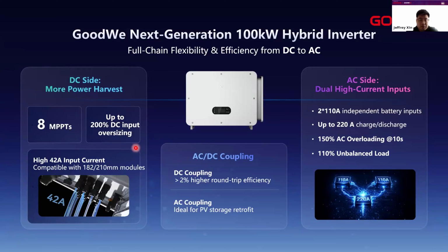That means you can connect more DC input from the PV panel, and for this 200%, there will be no wasted output, because that 200% can be used to fill the output together with battery charging. For example, 100% can be used for consumption or output to the grid, and another 100% can be used for charging. That means no power is wasted from the PV panels.